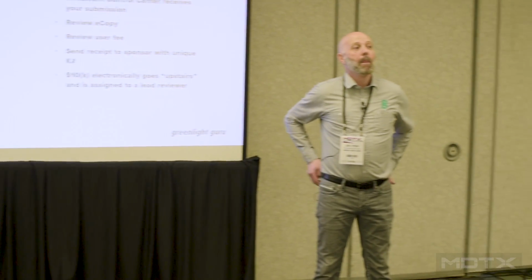So the first page or so of your submission is your receipt that you paid that. Yeah. What's the street pay? About 300,000 for a PMA if you don't follow. De novo about 90,000. So do they give breaks to startups? I mean, that's a lot for a startup. And that's part of the small business designation. But wouldn't a lot of startups go the de novo because they're developing something completely new? Yeah. This is reminding us that the first de novo is also free.